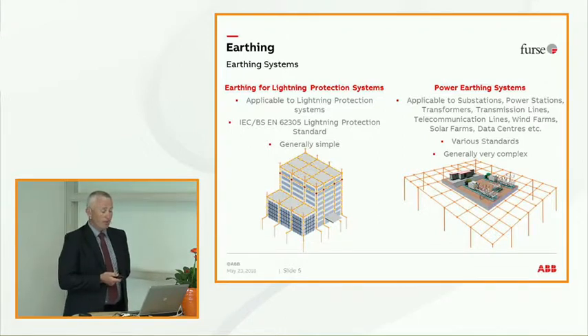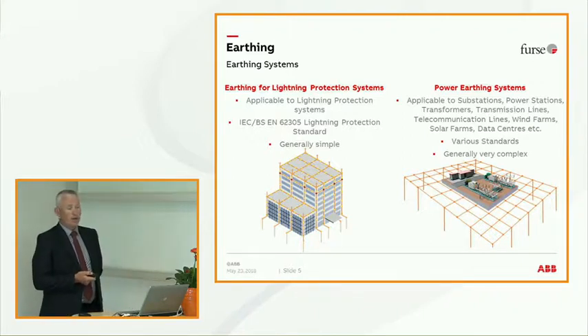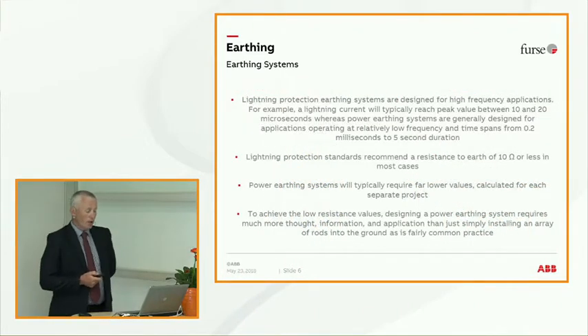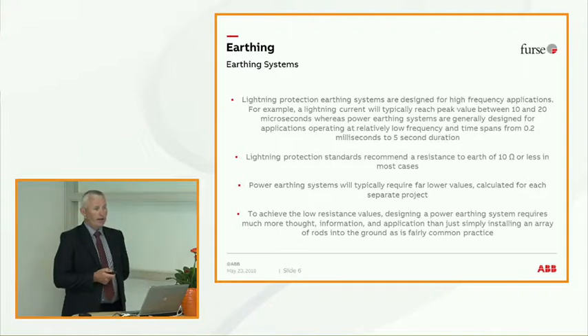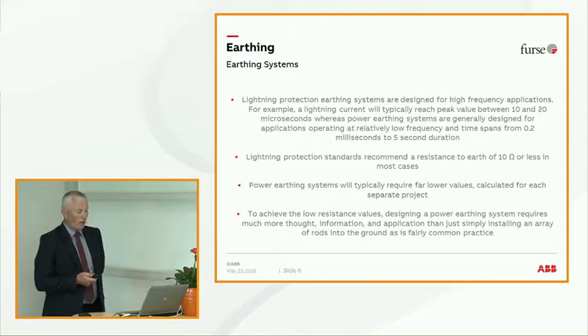Power earthing systems are applicable to everything that supplies power: your substations, your power stations, your transformers, again solar farms, data centres. The difference is that with lightning protection, the lightning strike is very, very quick. It's 10, 20 microseconds, so the system is designed to accommodate such a short duration. A high temperature is not really applicable because it's a fast strike, and the idea of the system is just to take that to Earth as quickly as possible. Remember, when we talk about Earth, we're always looking at the least resistance to Earth, the quickest path to Earth. So it's all about bonding, about allowing the current to flow equally.